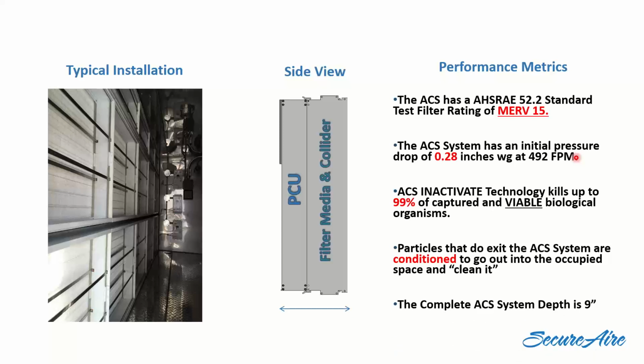It is a Merv 15, which is great, way better than what ASHRAE recommends for COVID purposes. And the nice thing is it only has a pressure drop of 0.28 inches. For those who don't work with air handling equipment, that might not mean much, but it's pretty similar to a normal filter. Really low-end filters have like 0.1 or 0.15. So this has more pressure drop than a regular filter, but it's nothing like a HEPA, where you'd have between 0.6 and 1.2 inches of pressure drop.